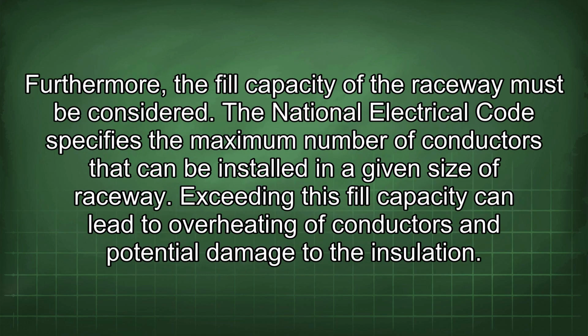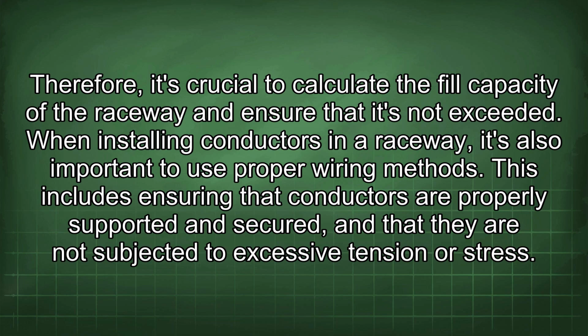Furthermore, the fill capacity of the raceway must be considered. The National Electrical Code specifies the maximum number of conductors that can be installed in a given size of raceway. Exceeding this fill capacity can lead to overheating of conductors and potential damage to the insulation. Therefore, it's crucial to calculate the fill capacity of the raceway and ensure that it's not exceeded.